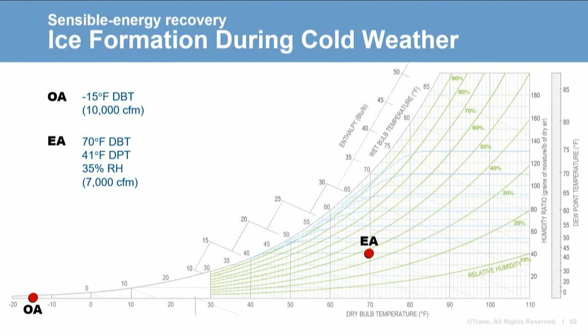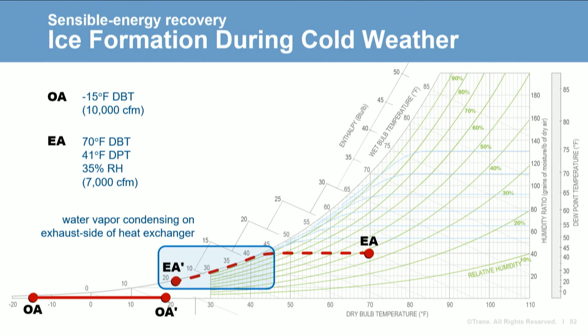During very cold weather, as more heat is removed from the exhaust airstream and transferred to the outdoor air, the exhaust air can cool to the point where it reaches a saturated condition. In a sensible energy recovery device where exhaust air is at 70°F dry bulb and a 41-degree dew point — equating to 35% relative humidity — as the exhaust air cools below 41°F dry bulb, it reaches saturation and water vapor begins to condense on the exhaust side of the device. If the surface temperature is below 32°F, this condensate will freeze, eventually blocking airflow and possibly damaging the device.